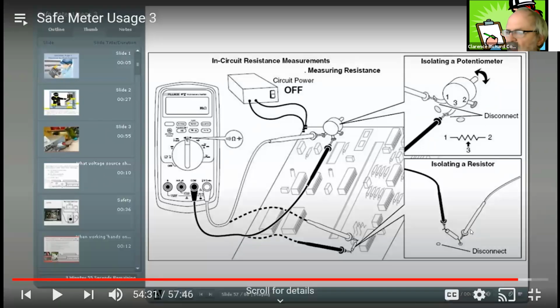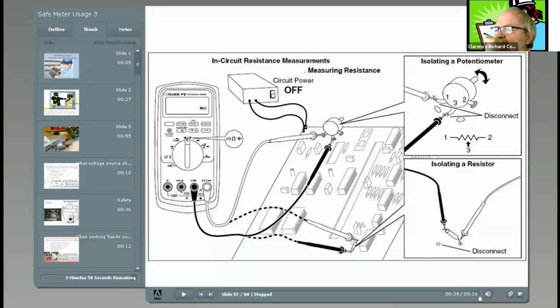Sometimes isolating something, you have to really unsolder it and then take it. You guys had one of those fuses that was, I don't know, you don't solder those in there. Those little fuses on those I/O boards just pop in and out. To measure resistance, set up the meter as shown in this slide.